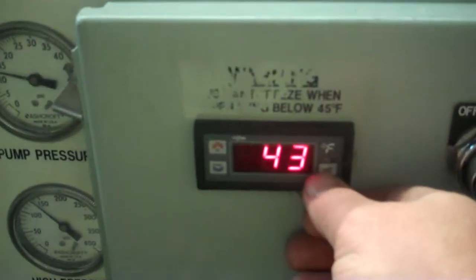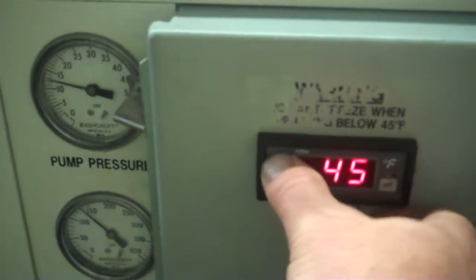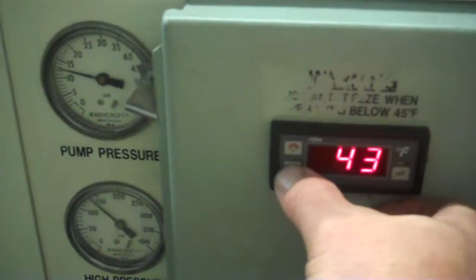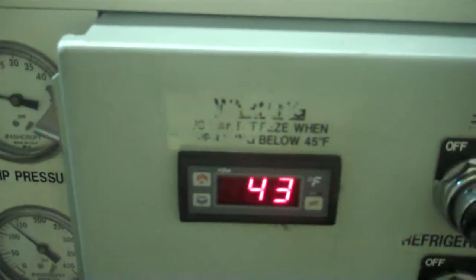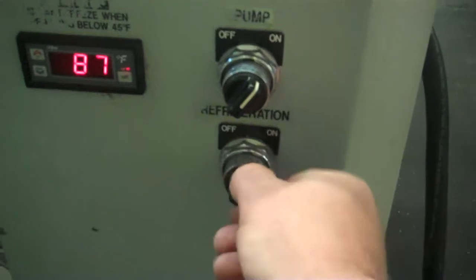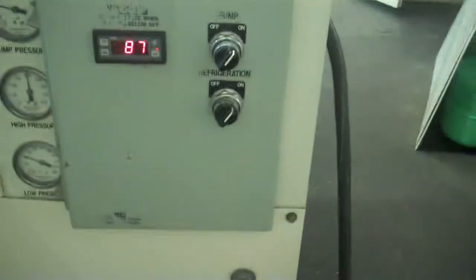We're going to go ahead and change the set point. Well, it's at 43 right now, but to change it, you just press that set button, go higher and lower. So we're at 43. And for us to start cooling, you just simply take the refrigeration switch here, turn it to the on position. Getting maybe a tiny rattle here because this cover we don't have screwed down yet because we haven't prepared it for shipping yet. But both condenser fans are on and our compressor's on, and we're starting to chill.